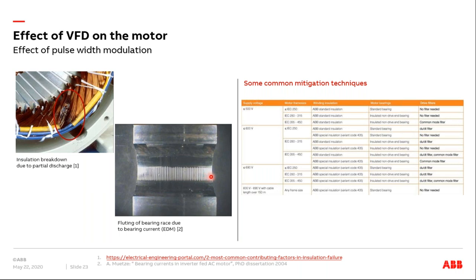You basically create a small spark, and what it creates on the bearing is what we call fluting of the bearing race. It damages the bearing in the long run, so you will have premature failures of your bearing also.